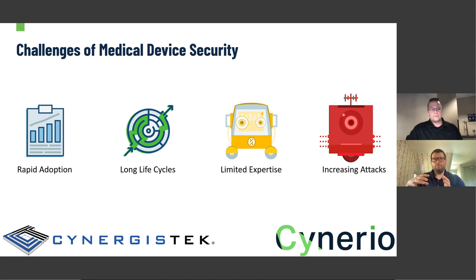To really paint that picture — patching one IV pump doesn't sound like a big deal, but hospitals have hundreds, in many cases thousands of infusion pumps. Constantly applying patches, which are already late to the game for previously identified vulnerabilities, is really difficult from a logistical standpoint. And as we get into more IoT devices, Windows is just a small sliver — around 7% to 10%. We see a lot of different versions of Linux and homebrew operating systems. The traditional methods used to protect a desktop at a nurse's station simply can't be applied in a reasonable way to all these devices propagating within healthcare environments. The high percentage is a customized proprietary Linux box, and the amount of information needed to protect that is difficult.